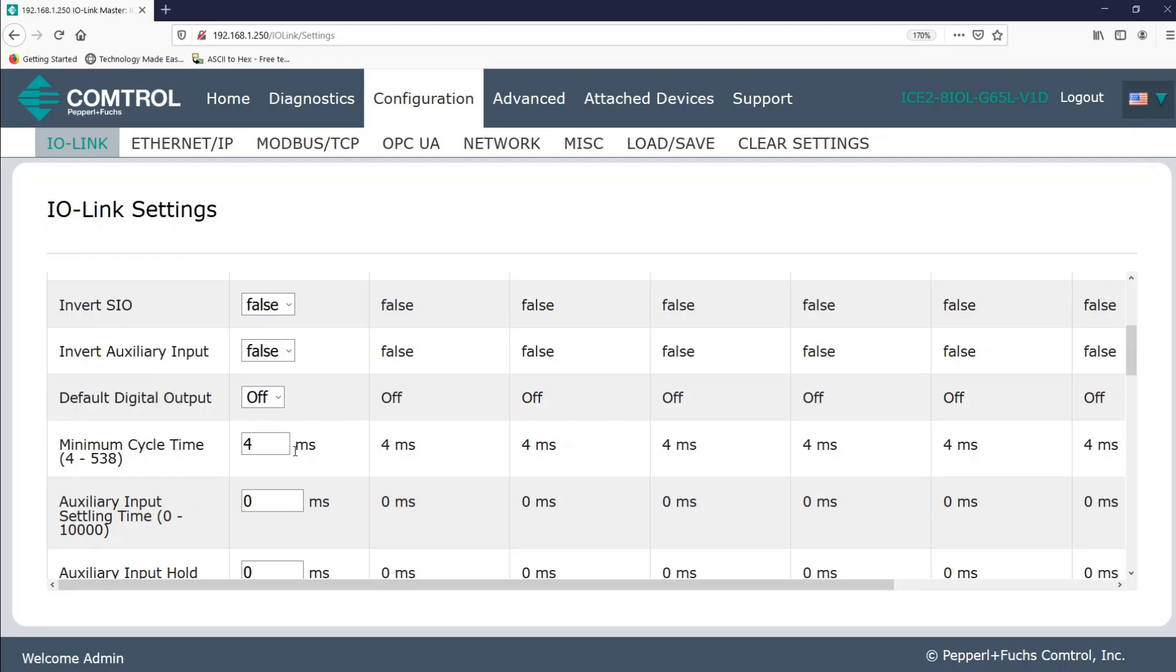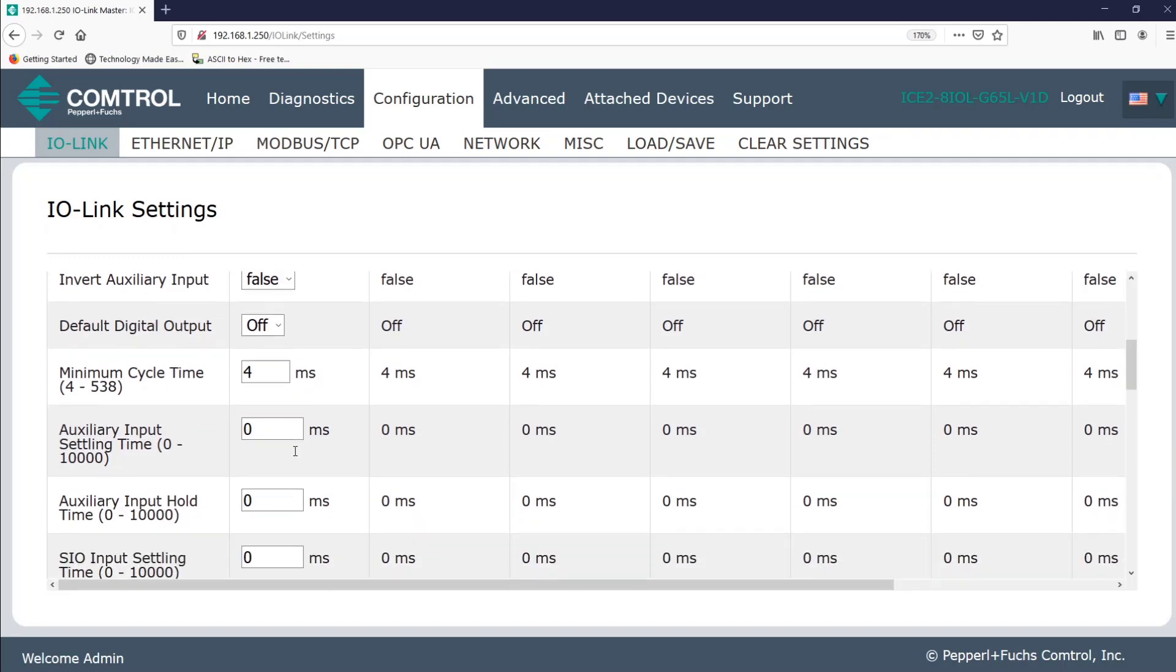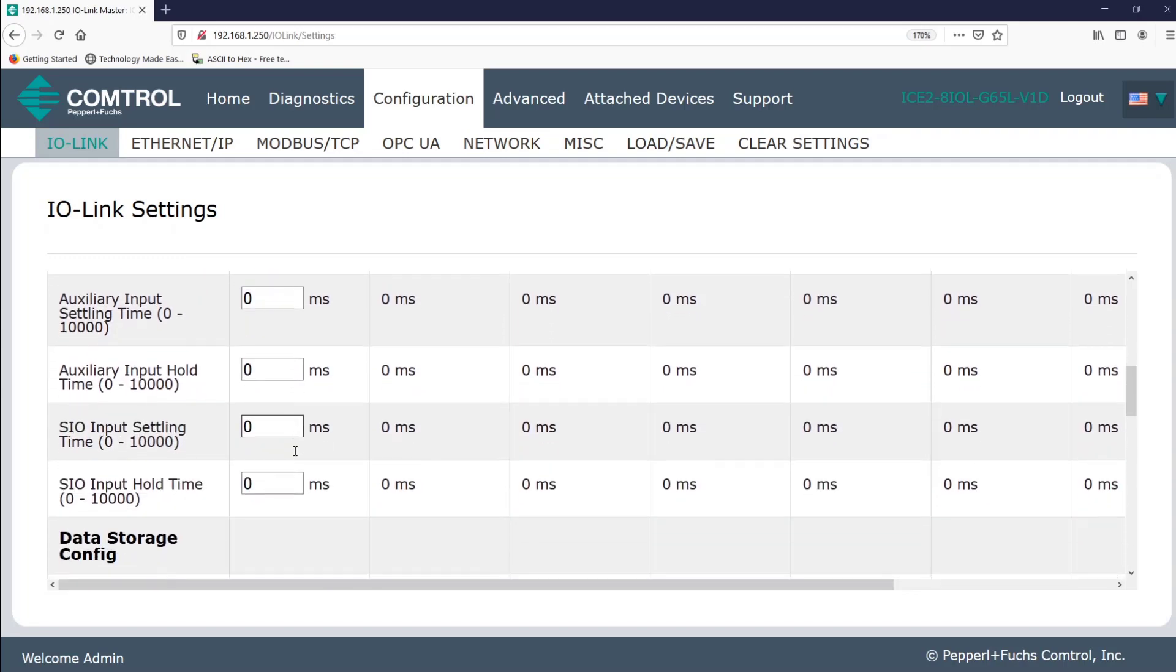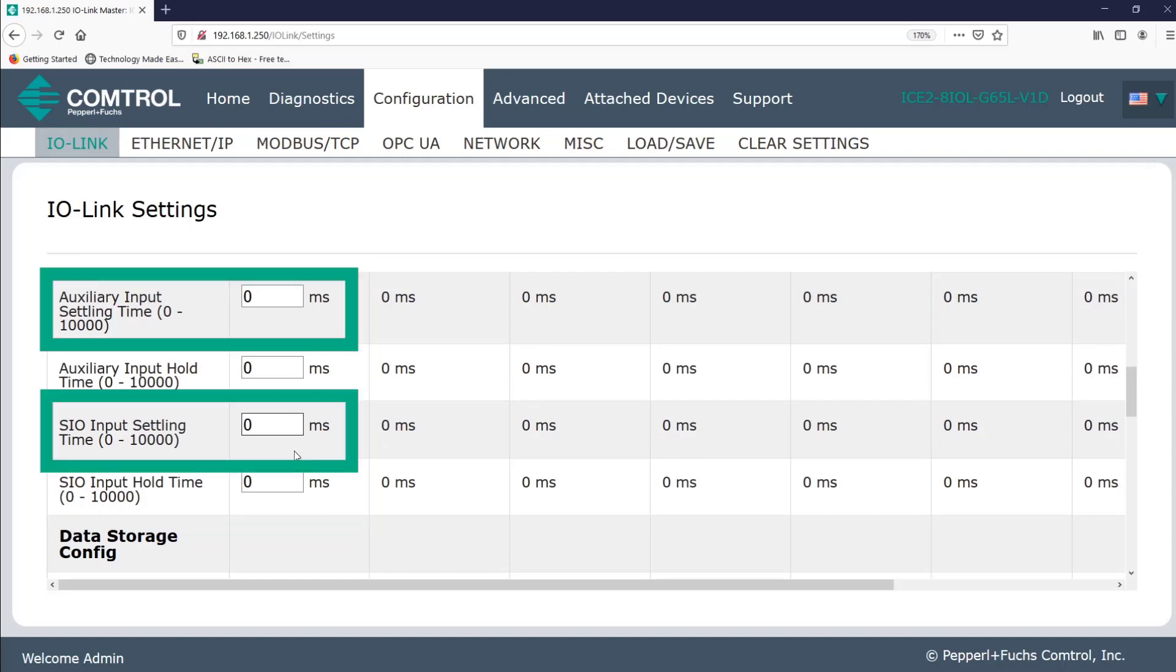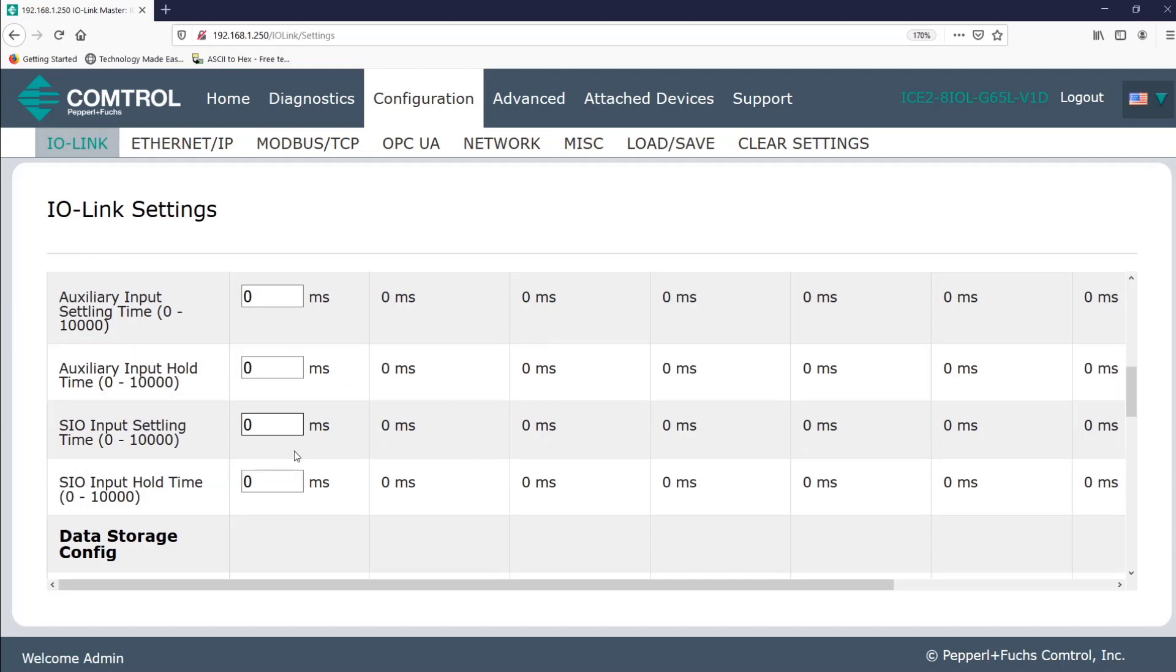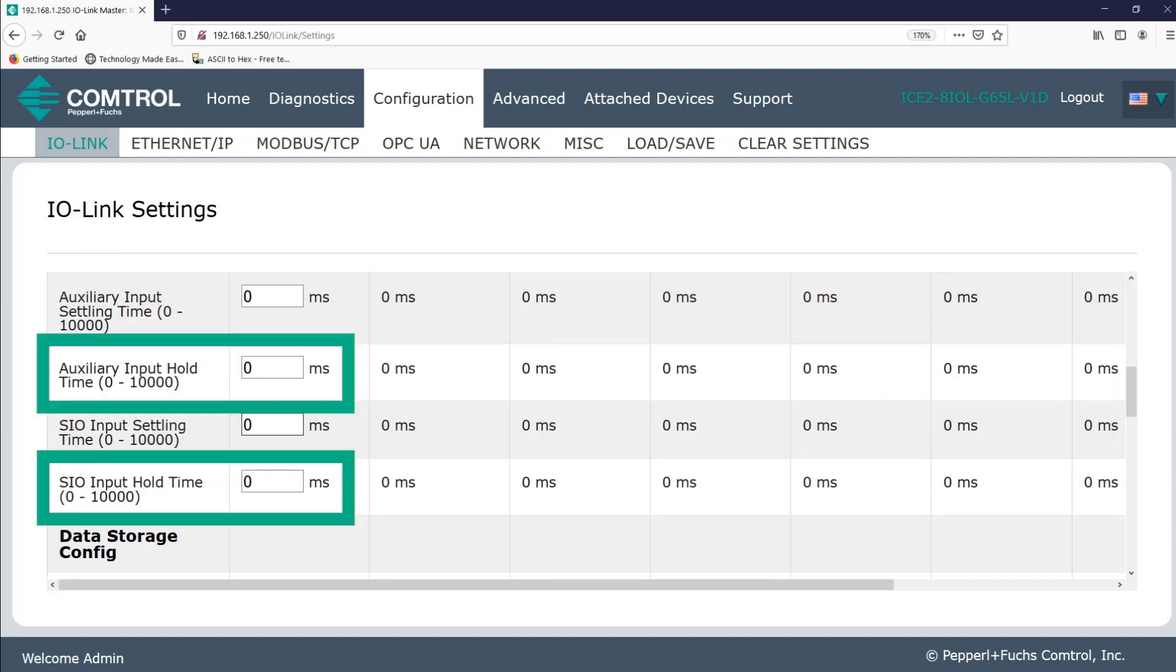So these next four settings allow me to basically set up two different ways of processing my data. One, for an input to be valid, the input needs to be present for the time specified under input settling time. Notice you have options for both the auxiliary input and the SIO signal. And two, once I have a valid input, the IO link master should keep a hold of that value or data for the specified input hold time. Again, this is just giving us more flexibility with how we interact with our data.